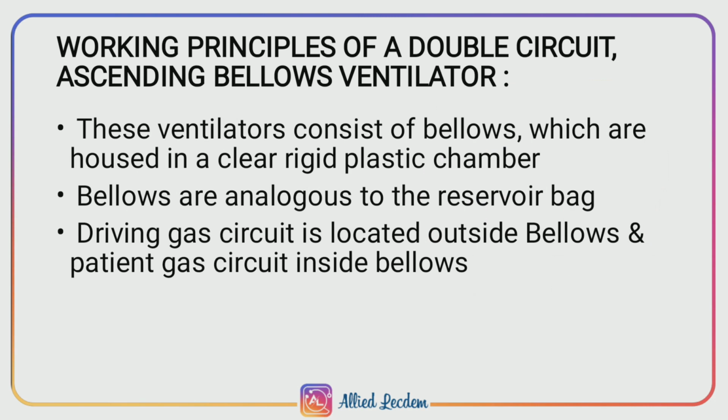Working principle of a double circuit ascending bellows ventilator. The ventilator consists of a bellows which is contained in a rigid plastic chamber. In some aspects, bellows are similar to a reservoir bag. Just imagine there is a plastic container, which is the chamber, and in it we have the bellows. So the driving gas is located outside the bellows but within the plastic chamber, and the patient gas circuit is typically inside the bellows itself.